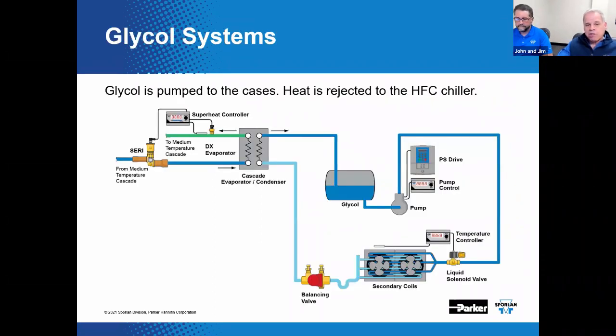Now, on to solutions for the problem of global warming. Using glycol as a secondary fluid was one way to reduce the refrigerant charge in a system and help address the GWP concern. This particular method was a thing for a while, the so-called secondary glycol system, as we've depicted here. Essentially, this is similar to a chiller system, and the mechanical refrigeration plant, off the schematic, is used to cool the glycol water mix that would be circulated through the store. Now, no phase change occurs on the glycol water side of the system. And when the temperature is satisfied, the liquid line solenoid valve here would close and stop flow.